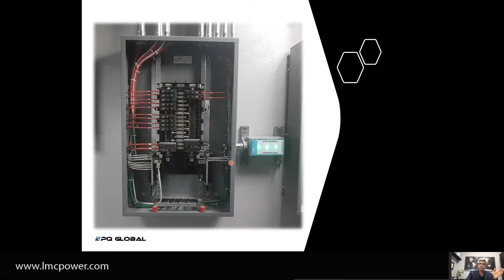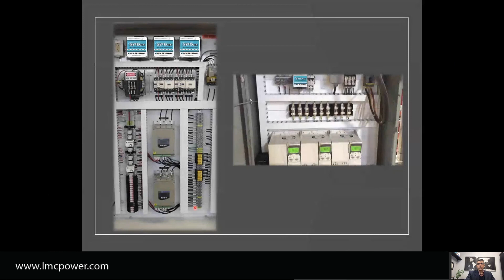So that was category C. Here's the same building, category B. They have a smaller panel distributing power to a little data center, a little computer room. Again, power will go in through here, and we have a short circuit to ground. Anytime there's a transient, it will create an instantaneous short circuit that provides a path to ground with least resistance. Category C, category B. A lot of our industrial customers liked our category A. In that same bank, I didn't get a picture of it, but they put their category A surge protection next to their security equipment and next to their ATMs. I'll show you right now one of their drawings to see where they installed it.